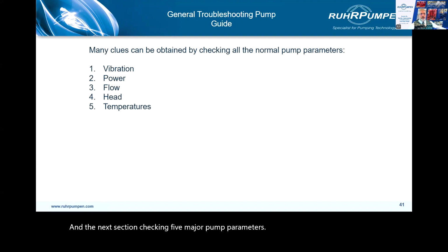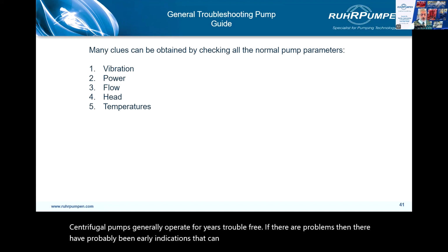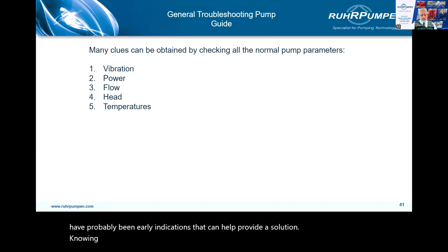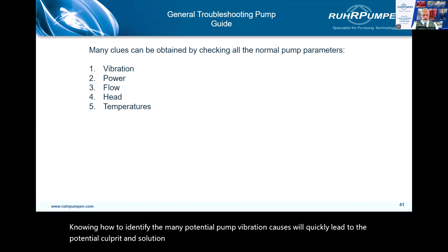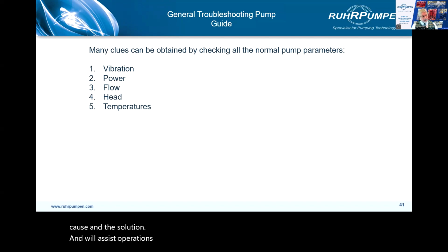Centrifugal pumps generally operate for years trouble-free. If there are problems, then there have probably been early indications that can help provide a solution. Knowing how to identify the many potential pump vibration causes will quickly lead to the potential culprit and solution. These slides are intended to give guidance as to the likely cause and the solution, and will assist operations, maintenance, and the pump and seal vendors' customer service guys to efficiently solve the problem. So vibration, power, flow, head, and temperature.